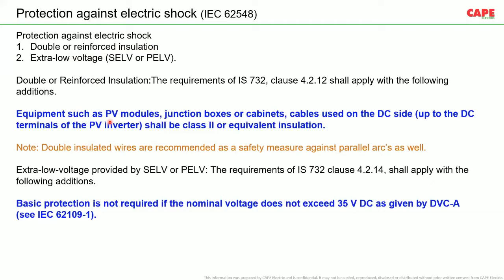For example, the PV junction box is plastic. The wire is having an insulation, and once you connect it to a terminal, of course, the enclosure is also plastic, double insulated material. This also means using metallic enclosures for the PV side, let us say, for example, a combiner box, will often be a violation of the requirement of class 2 electrical insulation. Double insulation will be compromised if you use, say, for example, a metallic electrical panel, a combiner panel.